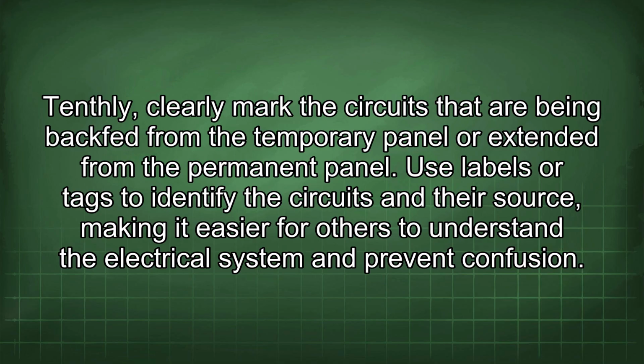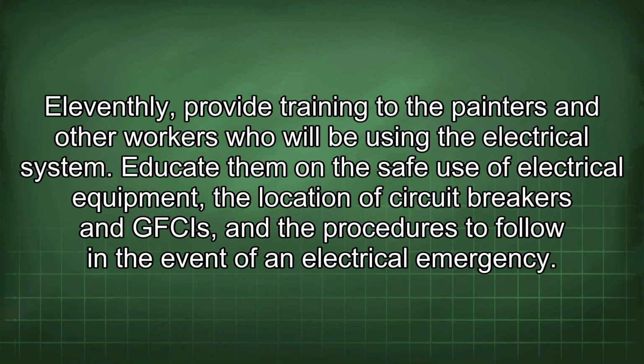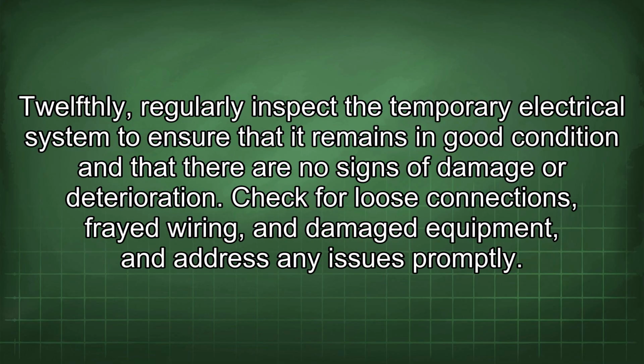Tenthly, clearly mark the circuits that are being backfed from the temporary panel or extended from the permanent panel. Use labels or tags to identify the circuits and their source, making it easier for others to understand the electrical system and prevent confusion. Eleventhly, provide training to the painters and other workers who will be using the electrical system. Educate them on the safe use of electrical equipment, the location of circuit breakers and GFCIs, and the procedures to follow in the event of an electrical emergency. Twelfthly, regularly inspect the temporary electrical system to ensure that it remains in good condition and that there are no signs of damage or deterioration. Check for loose connections, frayed wiring, and damaged equipment, and address any issues promptly.